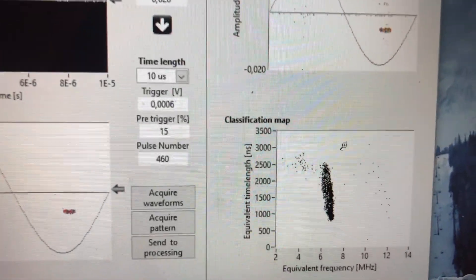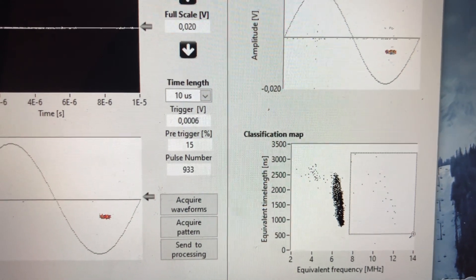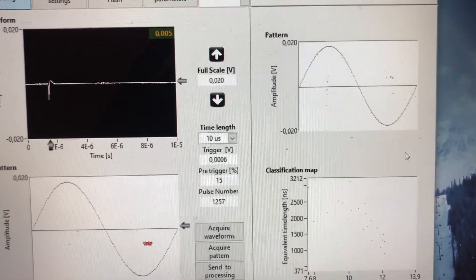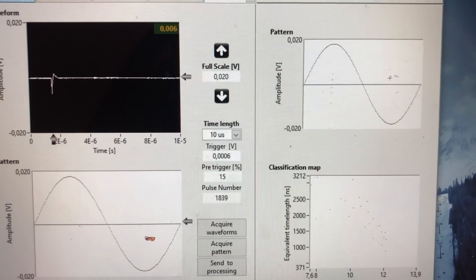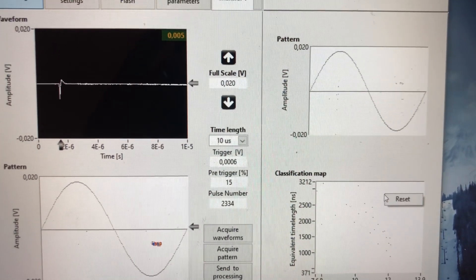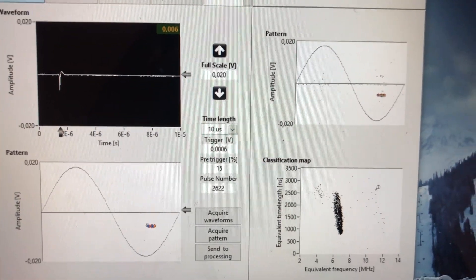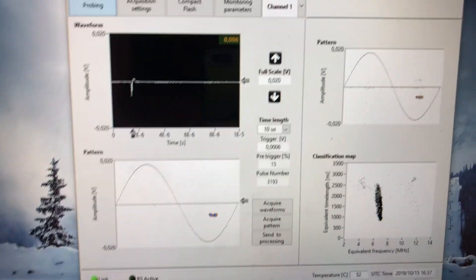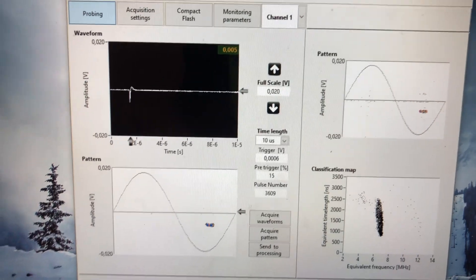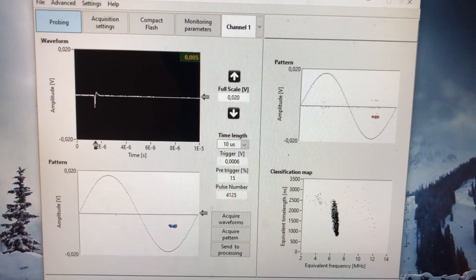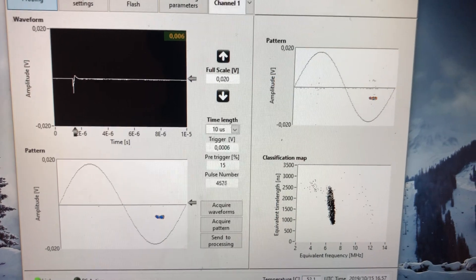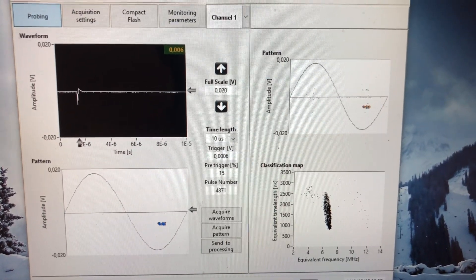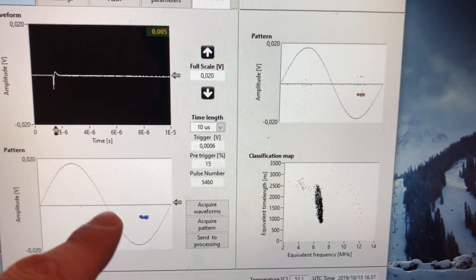Right now we also have this third cluster, which is, I suppose, noise. The only way to find out is to see what that represents. And we can see that it probably represents either noise or certain switching inside of the simulator. But let's not guess. Let's do another thing. We can now increase the voltage. By increasing the voltage, what I expect is to get not only a negative Corona, but also a positive Corona. The difference is that the negative Corona, which you can see here, will happen sooner than the positive side, because it's easier for this spike to emit electrons. This is the negative Corona, than to absorb electrons from the air.